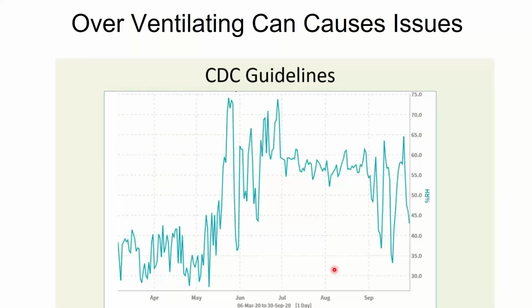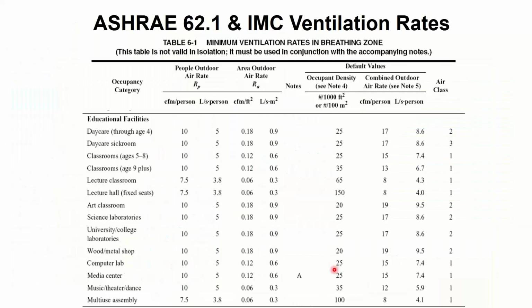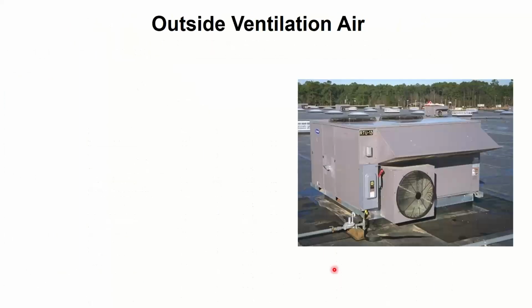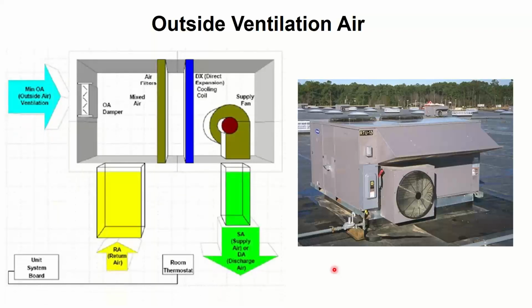I want to bring in the code required amount from those tables, and my equipment should be sized to handle that code required amount because somebody designed it that way originally. But if you want to bring in more outside air, we're going to have to take a look and see if your equipment can handle that properly. Otherwise you're going to have really cold spaces in winter and really humid spaces in spring, summer, fall.